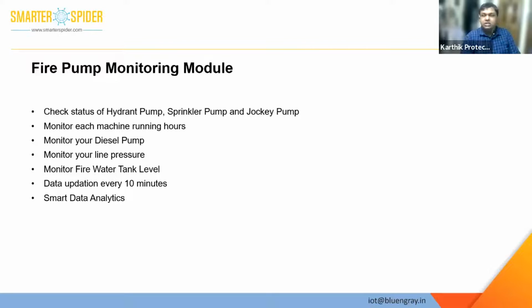In monitoring the diesel pump, you can monitor the current fuel level, how much fuel is poured, how much fuel is consumed during the runtime, the battery voltage, and the on/off status. Then monitor your line pressure. Basically, we provide this at the pump room, but if the client requires it at different locations too, we can provide that. And then monitor the fire water tank levels.